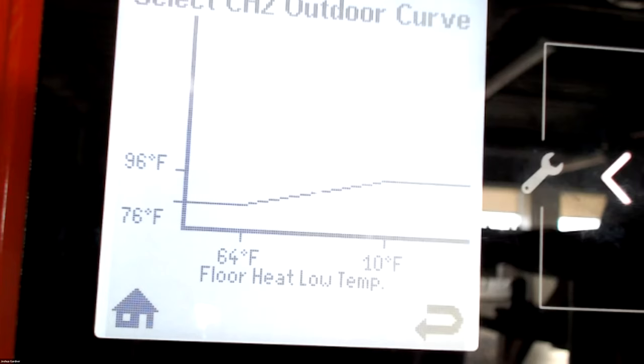So if you have those two differential temperatures, you need to install some sort of mixing, whether it's a static, you know, Honeywell AMX series mixing valve or Tecmar, whatever, to protect that low temperature heating. You still have to do that. But if you're, you know, a fan coil and baseboard, I might not worry about it. A fan coil can handle those higher temperatures. So you just got to watch out for that.